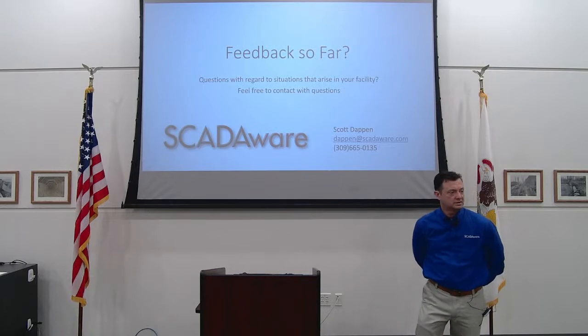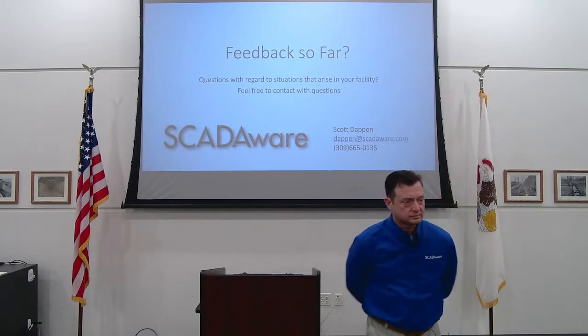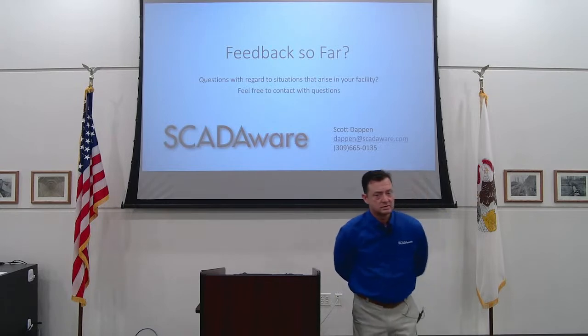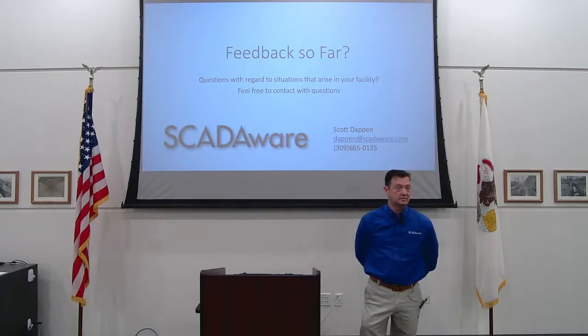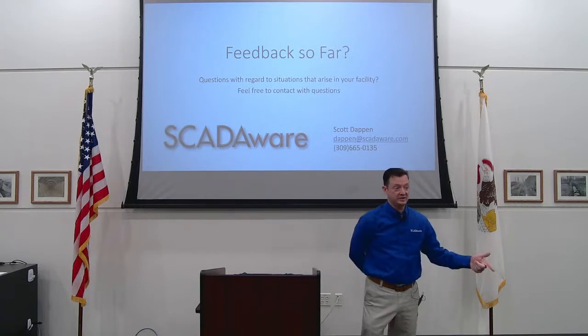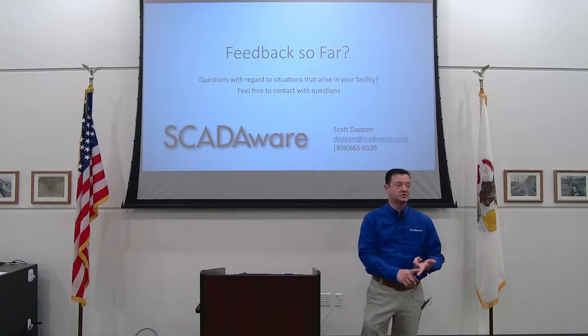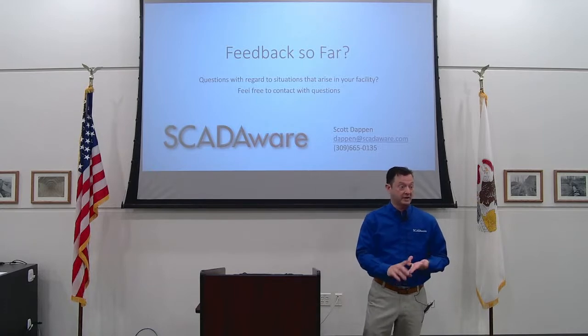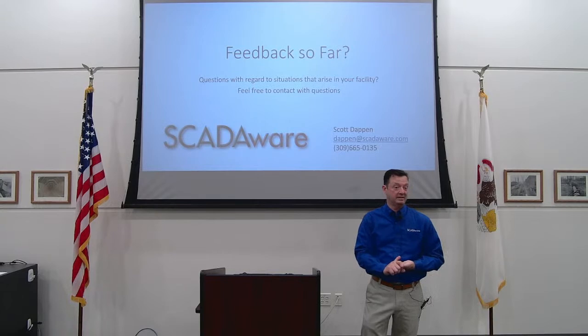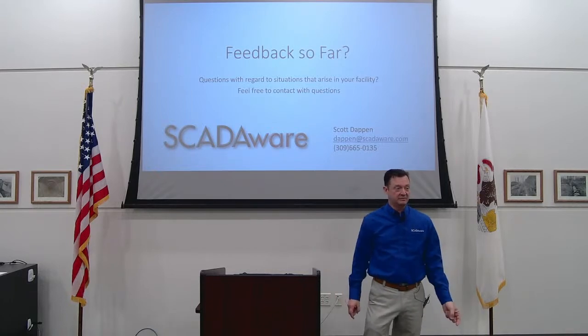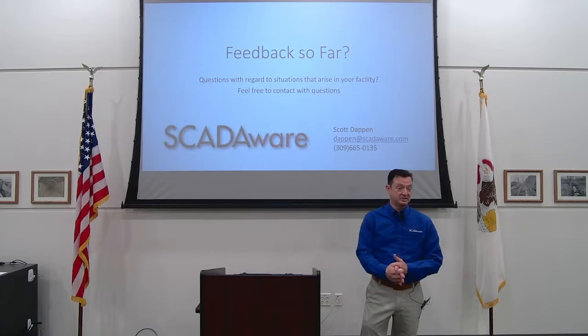What about a VFD fault? If you're having issues with codes on VFDs or programming on VFDs, who do you call? I would say it typically depends on the fault you're getting. If you're getting over voltage faults, or the VFD is showing overloads on the motor, or something that indicates a bad motor, then you'd probably just call an electrician out. But if it looks like a control problem where it's not seeing a signal come into it, it's probably better off calling an integrator for it.